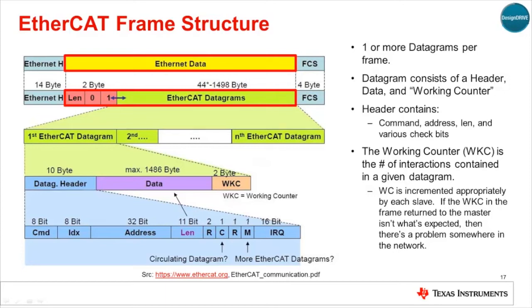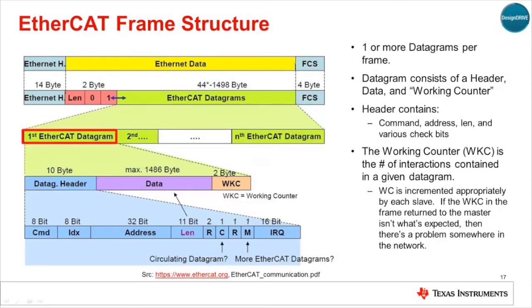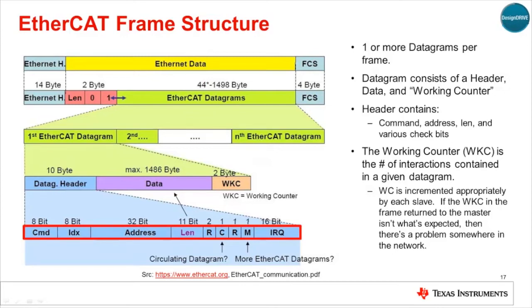Within a standard Ethernet frame, there are one or more EtherCAT datagrams carried in the payload section. Each datagram consists of a header — which contains the command, address, length, and various check bits to ensure the integrity of the network — the data to be transmitted, and a working counter, or WKC. The working counter indicates the number of transactions carried in the datagram. As the datagram makes its way through the EtherCAT slave nodes, each node addressed by that datagram will in turn increment this counter. If the WKC field in the frame returned to the master does not match what's expected, then an error somewhere in transmission or network nodes has been detected.